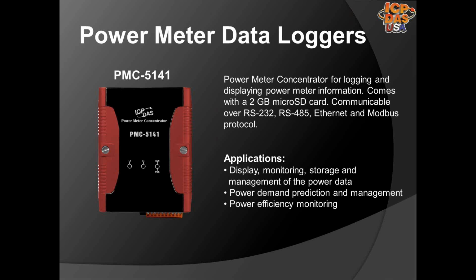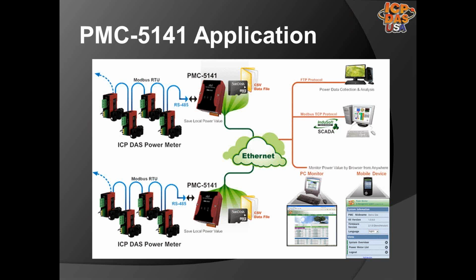PMC5141 supports up to 16 Modbus RTU-based devices. You can daisy chain Modbus RTU-based power meters over RS485. You can log the data on the micro SD card in a CSV data file. You can send the data logs back to a computer over FTP protocol or by email. You can get the data over SCADA software through Modbus TCP protocol. You can also monitor the data through a web browser or from a PC or mobile device.